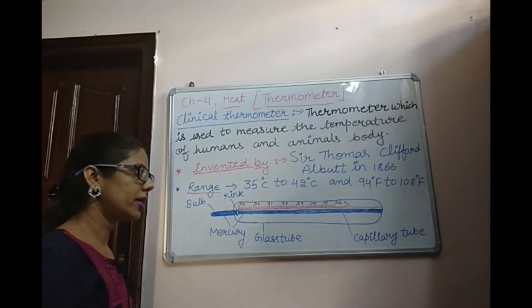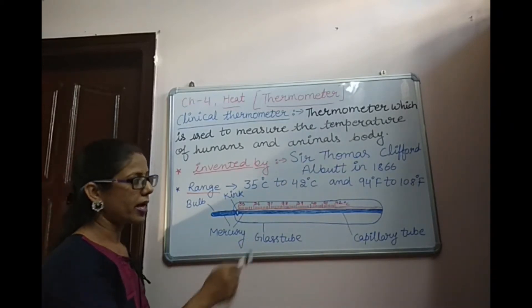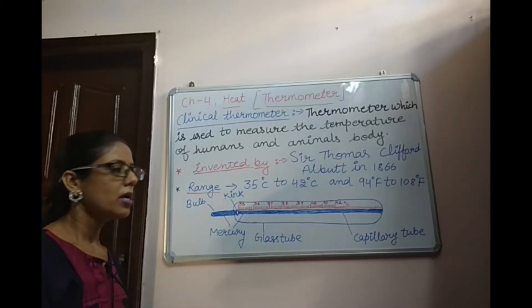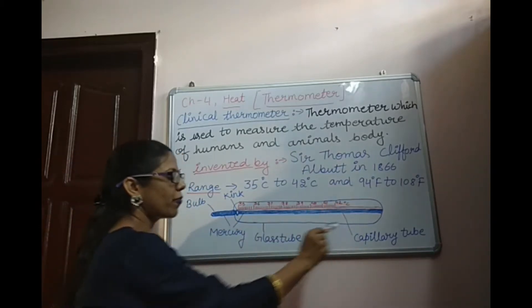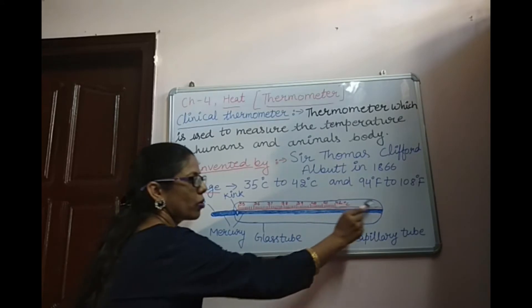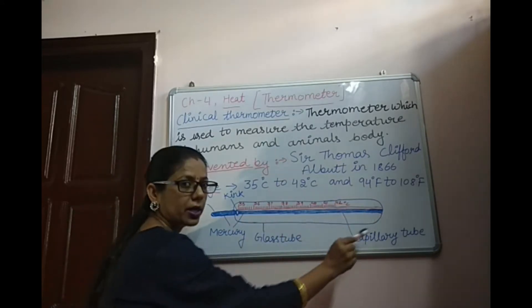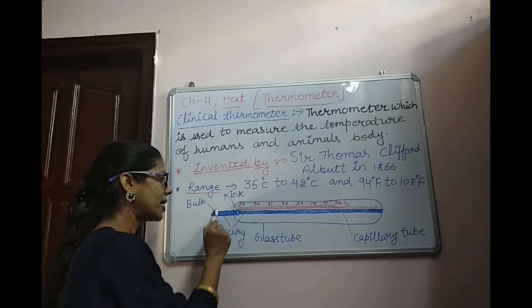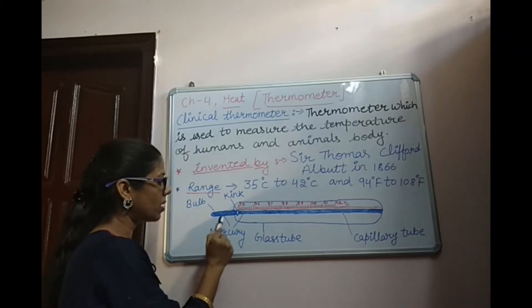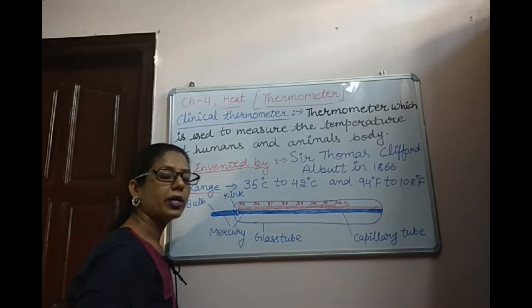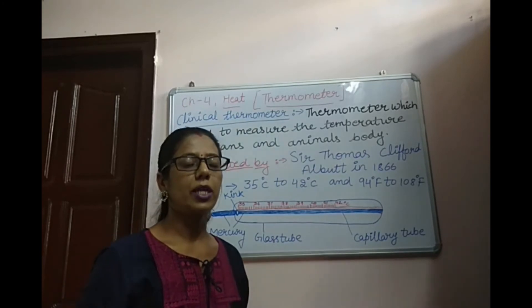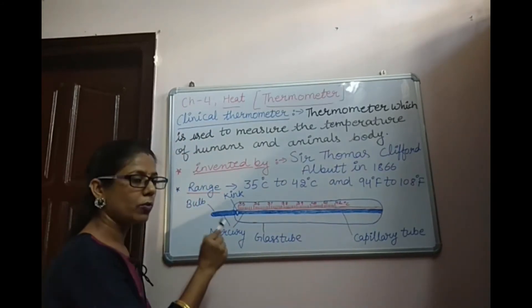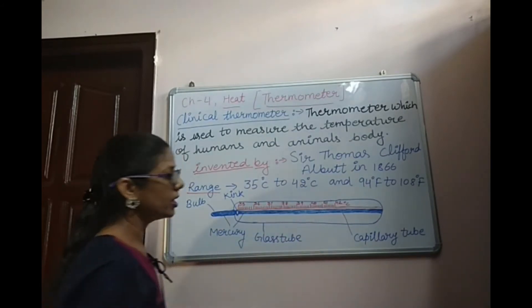Now, the structure of a Clinical Thermometer. You can see in the diagram the structure of a Clinical Thermometer. It is formed of a long and narrow glass tube. At one end of this glass tube, there is a bulb. This bulb is filled with mercury. Mercury is a metal which is liquid at low temperature, and it is filled in the bulb of the Clinical Thermometer.